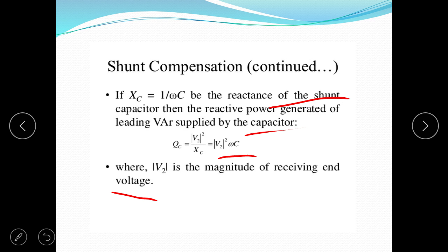So when load is small, or less than SIL loading, the load reactive power demand may be lesser than the reactive power generated by the line capacitor. Under these conditions, reactive power flow through the line becomes negative. The reactive power flows from the receiving end to the sending end, and the receiving end voltage is higher than the sending end voltage. This effect is known as the Ferranti effect. This is an important term. The voltage at the receiving end being higher than the sending end is known as the Ferranti effect, which is due to the reactive power flow from the receiving end to the sending end.